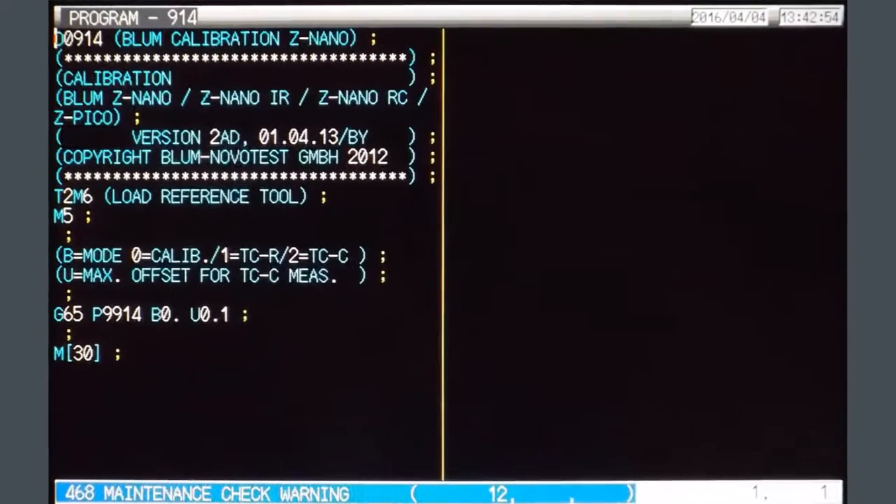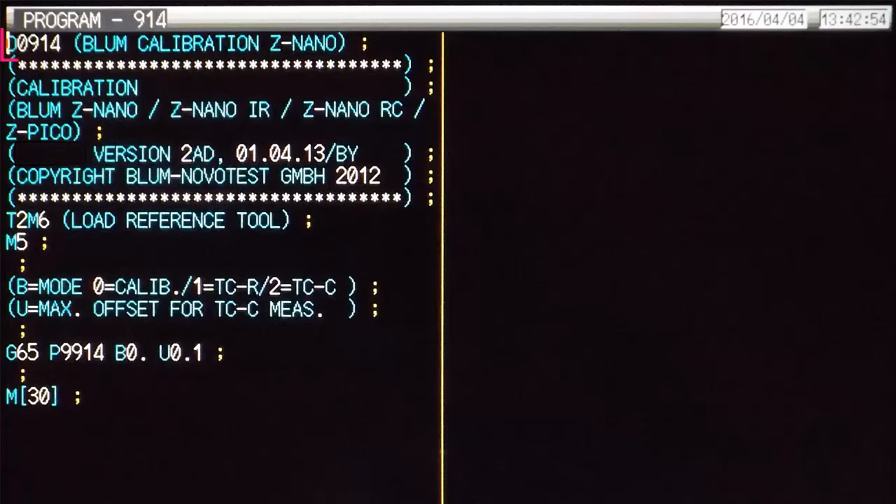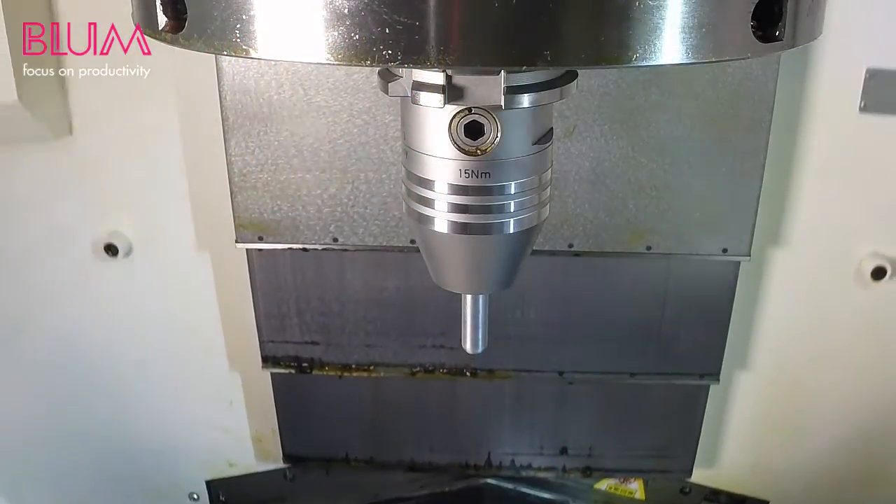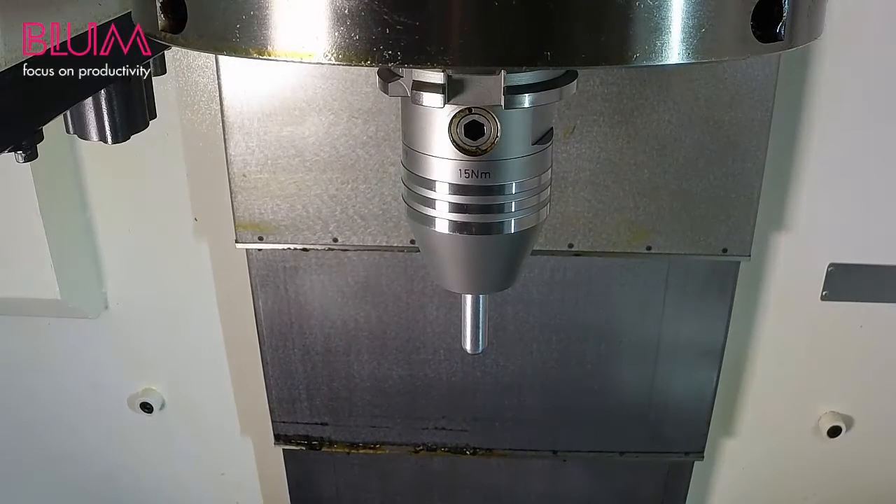To start, load in Blum's Z-Nano Calibration Program 0914. The Blum technician that set up your system will have already set up initial parameters, so it will run automatically. All that's needed is to execute the program using the provided calibration tool or a known artifact.